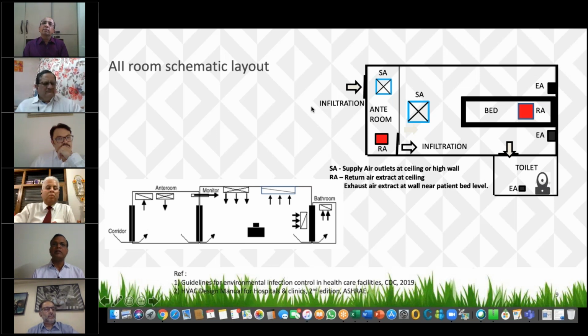ISHRAE suggests we can consider makeshift enclosures provided just over each patient, covering them individually. It would be a very light makeshift enclosure connected to a blower system and a HEPA filter system. The blower sucks air from the room into the enclosure, making the enclosure negative pressure, and it becomes a once-through system. The air is HEPA filtered and can either be let back into the same room or outside, depending on the air conditioning capability of the facility. This infrastructure suggestion has also been provided in the COVID document.